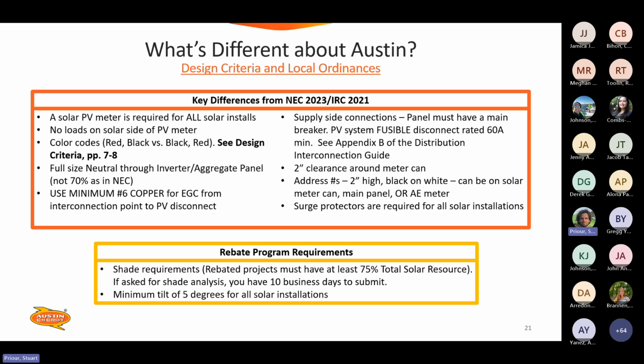Another important thing is the tilt of the modules of your array needs to be at least 5 degrees, and that's in line with the common manufacturer's instructions that will warranty modules only with at least a 5-degree tilt.